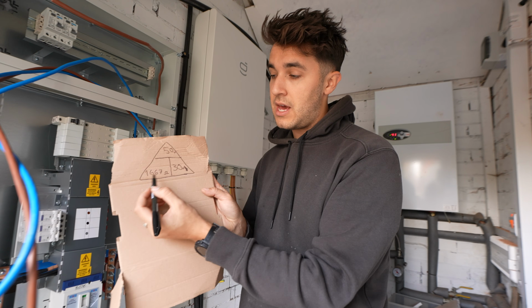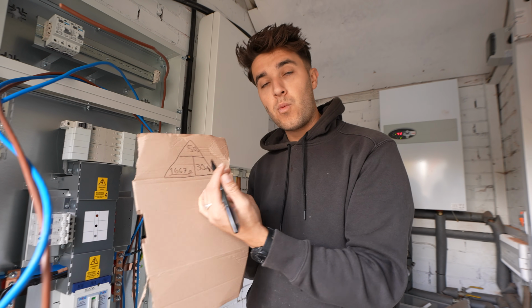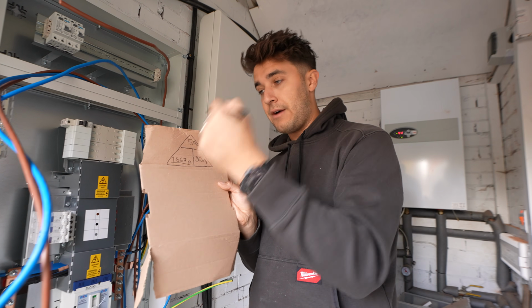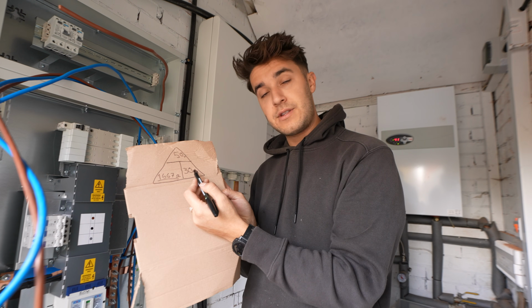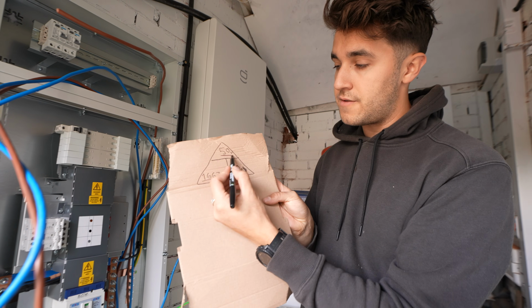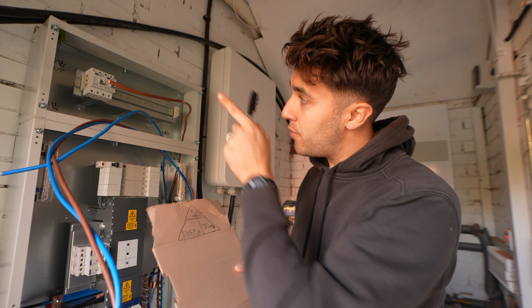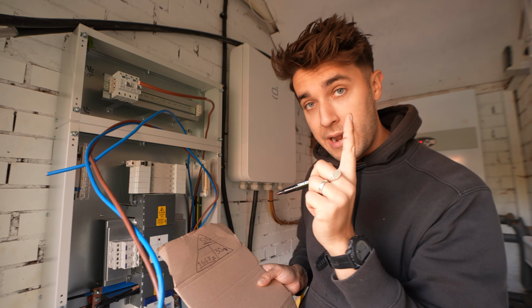That little equation with that magic number is why, when we say TT, you're technically allowed to go up to 1667 ohms if you have a 30 milliamp RCD, because we're trying to keep that touch voltage under 50 volts. We're going to answer the question, why have I gone for 100 milliamps here?